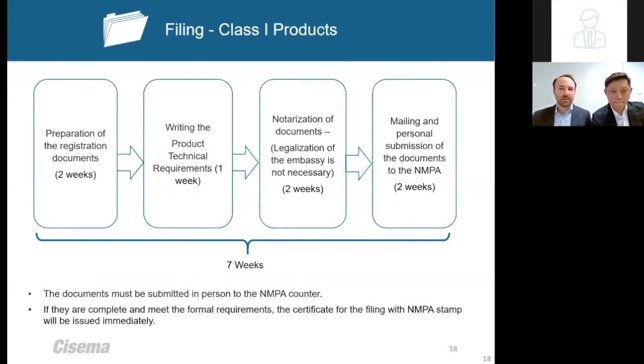So on this slide, we set out the Class 1 filing process in brief. Although we said 7 weeks for the total timeline, this can be, more generally, 3 to 5 months. Class 1 products don't require local testing, which is very important, and it's a filing process only. The important step here is the writing of the product technical requirements, or PTR as it's known, and we'll talk a little bit more about that later. That's because it sets out the technical specifications of your product. The documents must be submitted in person to the NMPA counter. Once they're complete and provided they meet the formal requirements, the NMPA will issue the certificate on the spot. Notarization and the other administrative processes also take time, and that's part of the reason for the length of the filing process.